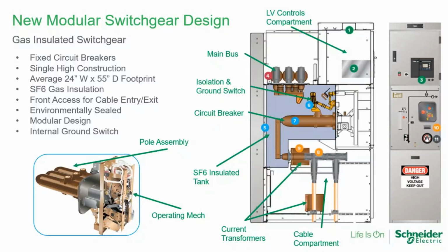Most of the gas insulated switchgear designs are single high construction. With GIS applications, you can get as small as 24 inches wide and 55 inches deep. And this is true all the way up to 38 kV. And at these higher voltage class ratings, that's really where this style of switchgear shines. The SF6 gas insulator is what's used as the main dielectric throughout the gear in order to calculate phase separation and phase differences. SF6 is used in those calculations as opposed to air separation.